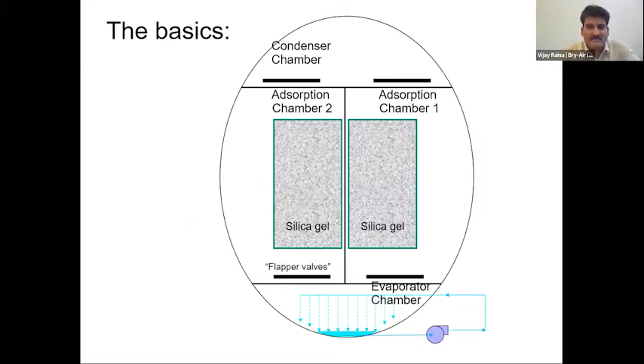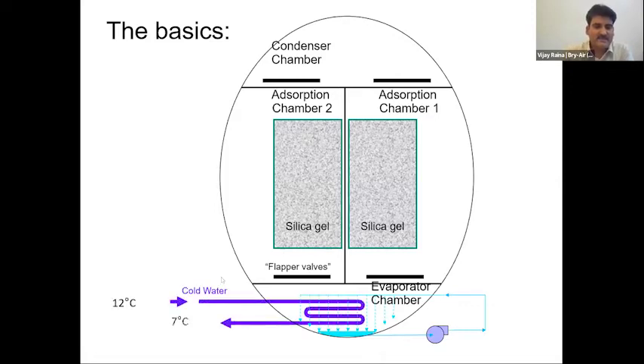There are three chambers. Below the chiller you see the evaporation chamber. On top is a condenser chamber, and in between there is silica gel filled in chamber 1 and chamber 2, which helps us to transfer the heat from the refrigerant evaporator to the condenser, and then again the same refrigerant comes back into the evaporation section to achieve the chilled water desired for the cooling application. For example, we are getting 12 degrees from the AHU or from the process cooling heat exchanger, and we are giving continuously 7 degrees. When this process is happening, our evaporation chamber is already filled with refrigerant water, and then this refrigerant water gets evaporated with the help of vacuum.